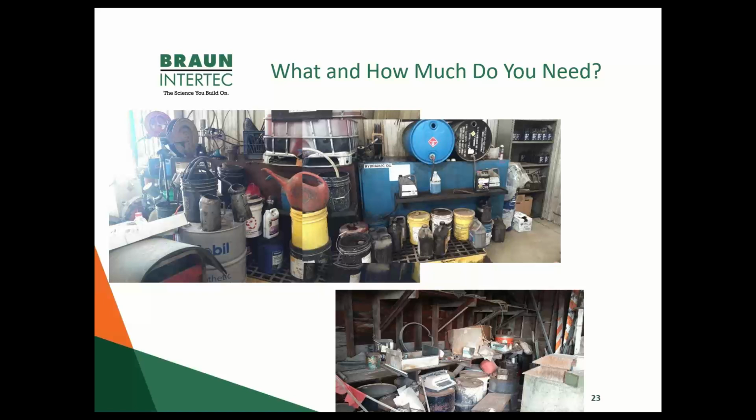So clearly these weren't in use, but because they were full of fluid, they still had to be included in the facility's total inventory. And additionally, because they weren't being used, they were largely forgotten about, but just waiting for those drums to rust through and start leaking into the ground or leaking out the back of the building and causing a concern.